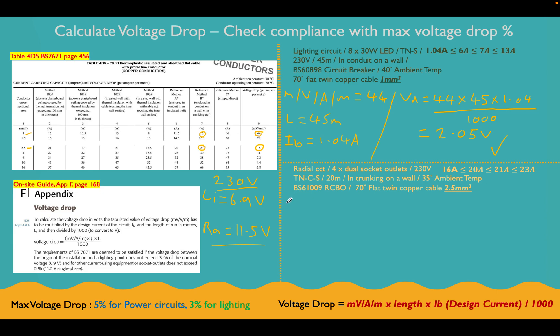Right, let's do this side now. So let's go again. So the millivolt amps per meter value for this one is 18. And then the length of our circuit for this radial circuit is 20 meters. And the design current for this circuit was 16 amps. That was our assumed load, 16 amps. So let's put a line straight across there. Let's go for this now.